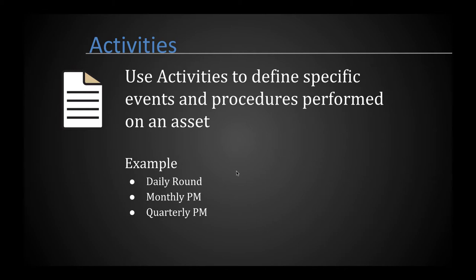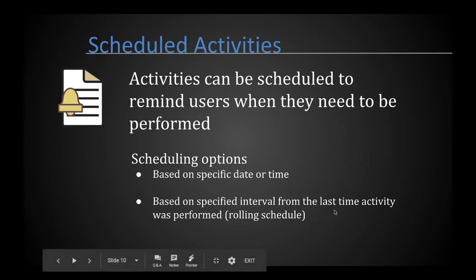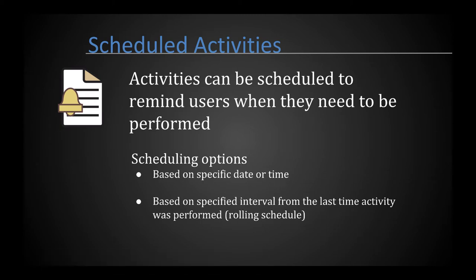An activity is the form where data will be entered, and you create one activity per event on that equipment. For a chiller, you might create an activity called 'daily round' for all data collected during the daily inspection. Because activities are mostly time-based, you can apply a schedule — either at a specific time such as 8 a.m. every morning, or on a rolling schedule where the next due date is a set number of hours from the last completion. These are your two scheduling options.